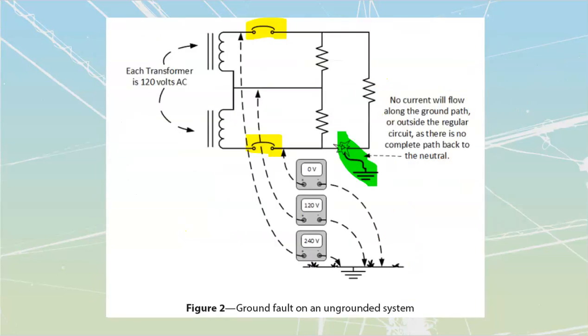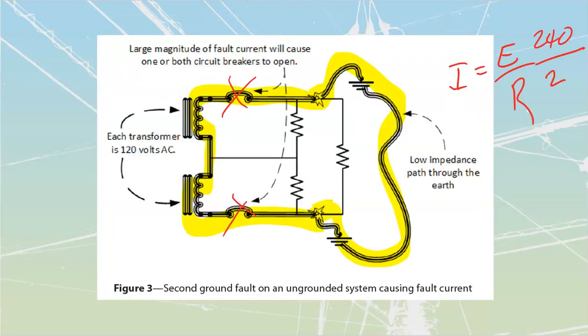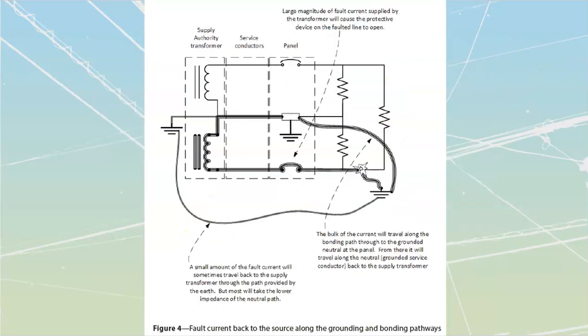Obviously, waiting for us to have one fault and then waiting for another fault is problematic. We don't want to have that, so that's why we start with that central solid ground that we have on the system. That way, by having this thing centrally and solidly grounded over here, we now have a path that is going to lead back to the neutral. Remember that current itself wants to always return back to the neutral. So if I end up with a fault, here's a live line that faults down to, we refer to it as ground, but in most cases it faults down to something that's bonded. The bulk of my current is going to travel back along the bonded pathway.